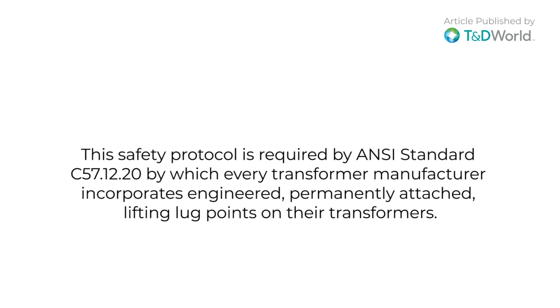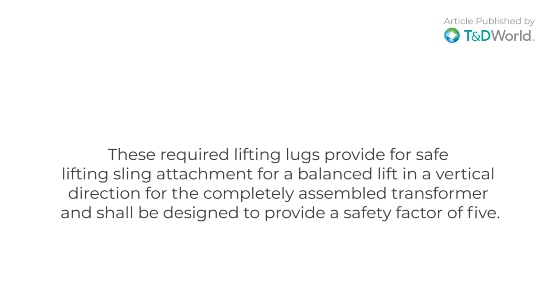This safety protocol is required by ANSI Standard C57.12.20, by which every transformer manufacturer incorporates engineered, permanently attached lifting lug points on their transformers. These required lifting lugs provide for safe lifting sling attachment for a balanced lift in a vertical direction for the completely assembled transformer and shall be designed to provide a safety factor of 5.